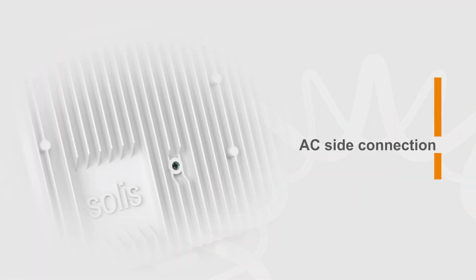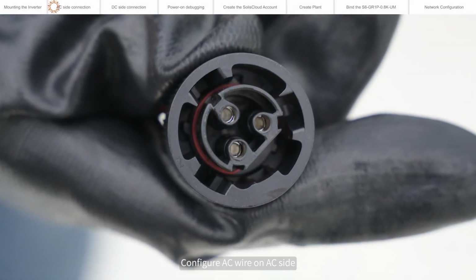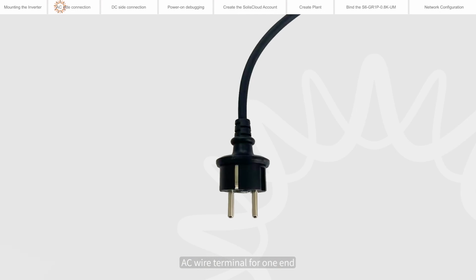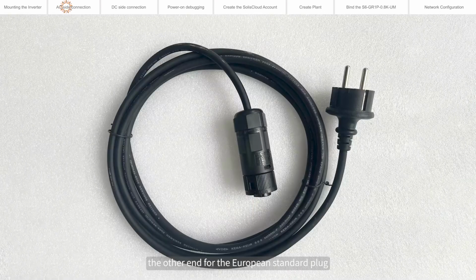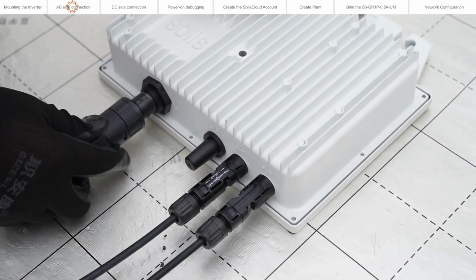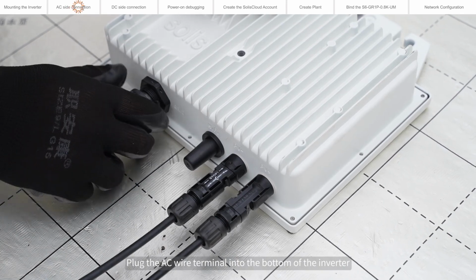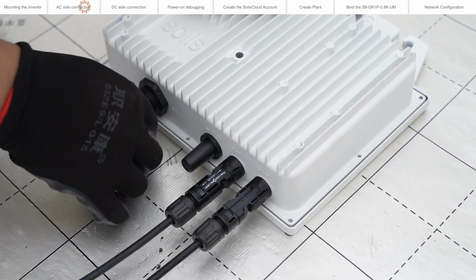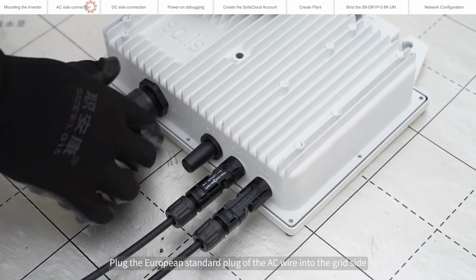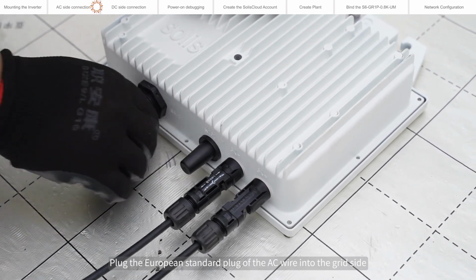AC side connection. Configure AC wire on AC side, AC wire terminal for one end, the other end for the European standard plug, wire length 3 meters. Plug the AC wire terminal into the bottom of the inverter. Plug the European standard plug of the AC wire into the grid side.